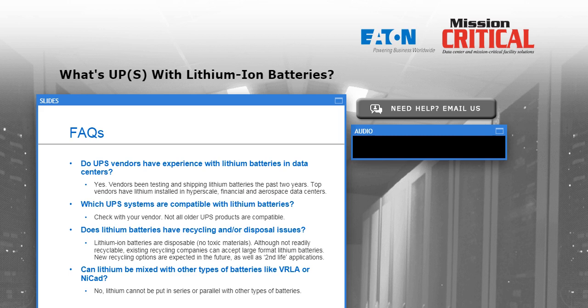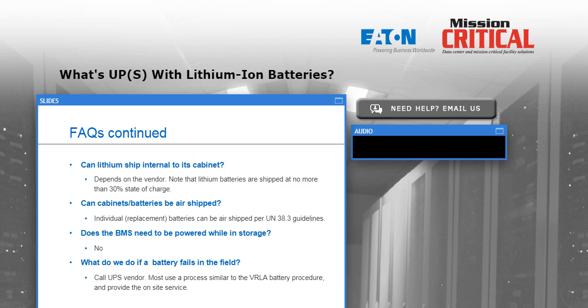Next question: Can lithium be mixed with other types of battery chemistries like valve-regulated, NiCad, or lead antimony? The answer is no. I don't want to put them in the same string or in the same parallel string with a different chemistry, and this is pretty much true for most battery chemistries. You really can't mix and match, at least not in a UPS application.